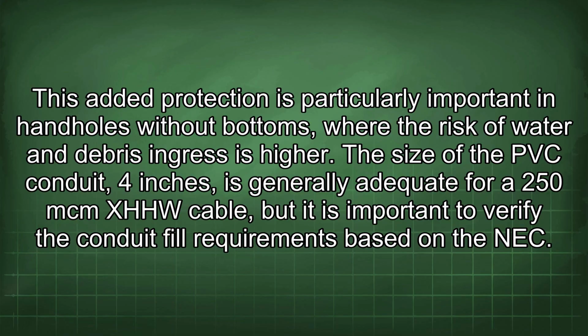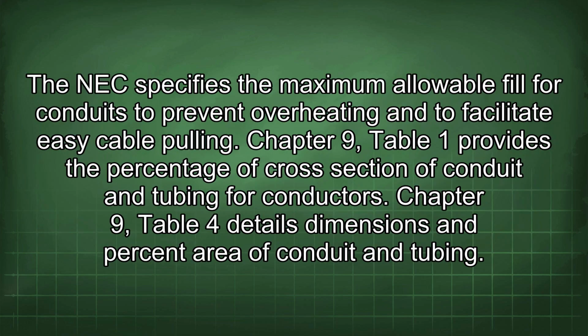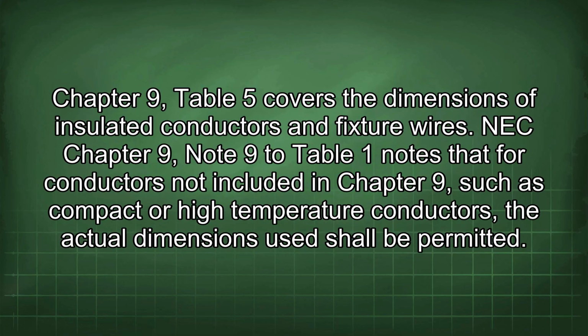The size of the PVC conduit, 4 inches, is generally adequate for a 250 mcm XHHW cable, but it is important to verify the conduit fill requirements based on the NEC. The NEC specifies the maximum allowable fill for conduits to prevent overheating and to facilitate easy cable pulling. Chapter 9, Table 1 provides the percentage of cross-section of conduit and tubing for conductors. Chapter 9, Table 4 details dimensions and percent area of conduit and tubing. Chapter 9, Table 5 covers the dimensions of insulated conductors and fixture wires.